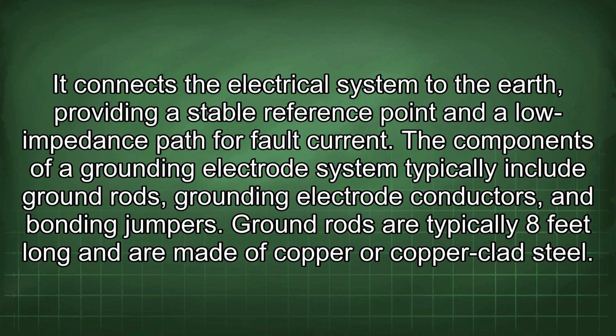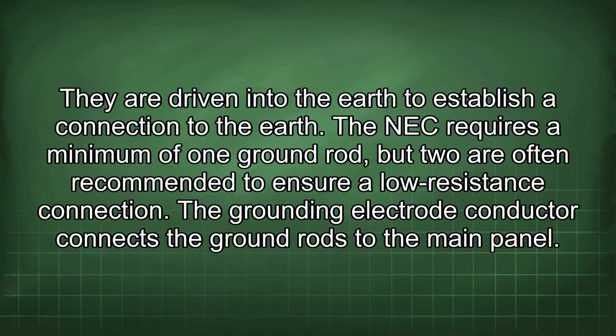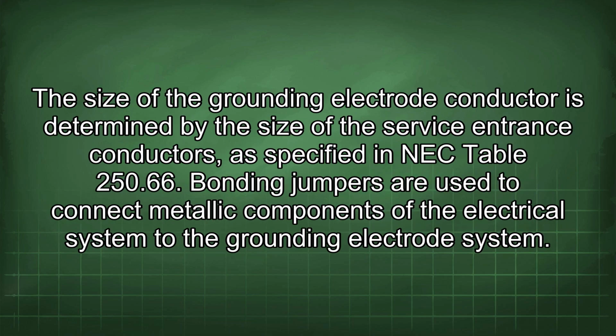Ground rods are typically 8 feet long and are made of copper or copper-clad steel. They are driven into the earth to establish a connection to the earth. The NEC requires a minimum of 1 ground rod, but 2 are often recommended to ensure a low resistance connection. The grounding electrode conductor connects the ground rods to the main panel.